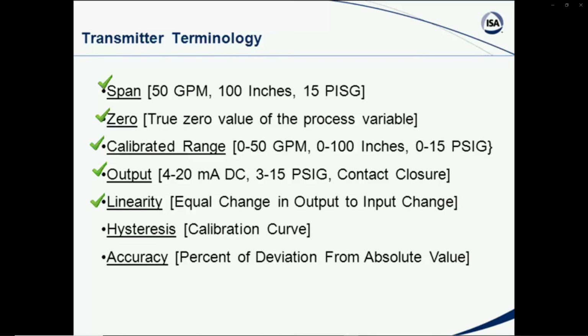And then sometimes you'll see them discuss or ask about the linearity of the transmitter. Basically that's the ability for the transmitter to have an equal change in output to an input change, or in other words, if you plotted the output versus the corresponding input that gave that output, it would draw a straight line from 0 to 100% of the input to 0 to 100% of the output. What happens in reality many times is that line is not exactly linear, and if you check the calibration points at 0, 25%, 50%, 75% on your way to the maximum input, and then come back down while you observe the outputs, you may get what's called a hysteresis, or nonlinear calibration curve. So that term we need to be aware of.